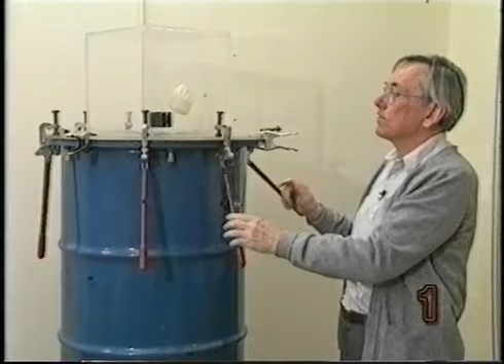This is schematically the plethysmograph. This inner ellipse is the speaker, and of course the speaker is connected to the outside through the face mask. This simulates a pressure transducer. So when the person is at the end of an expiration, most of the lung volume is at its minimum. There's a low pressure developed in the air around the person, so the pressure is low. When, however, the person is at the height of breathing in, has taken the greatest inspiration, their total body volume increases, particularly the chest, and that puts greater pressure on the air around the outside, so a greater pressure is developed.